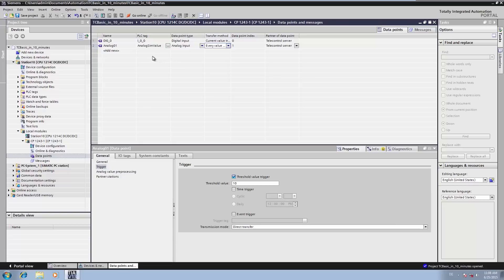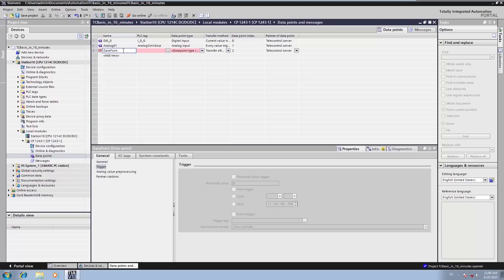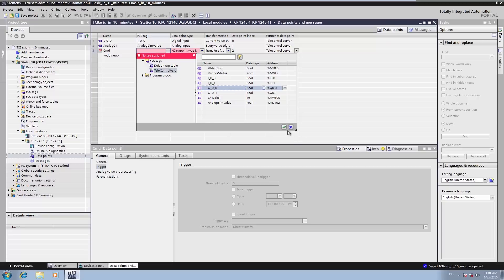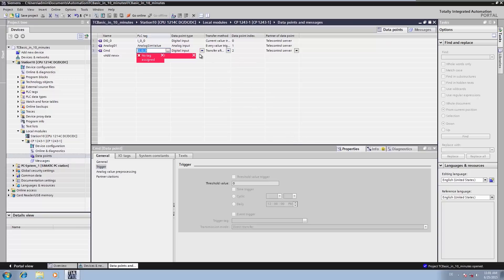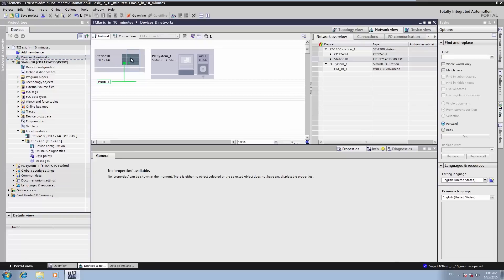In order to receive a command from the Telecontrol Server BASIC, we create a data point of the type digital output. We then link this point directly to the digital output of the CPU. This enables the command to be output directly to the digital output of the CPU. Now our SIMATIC S7-1200 station is completely configured and can be loaded.